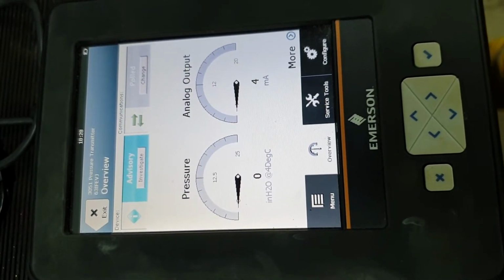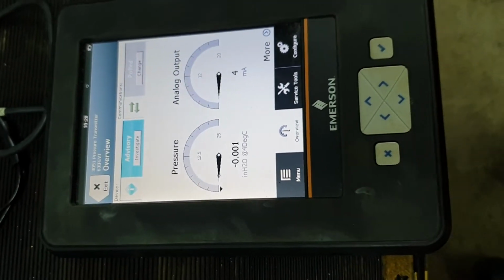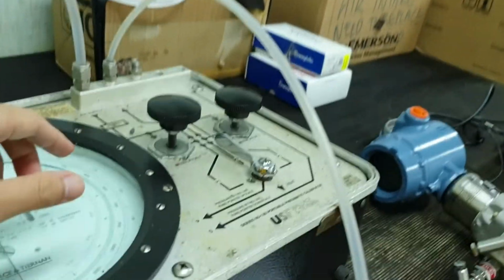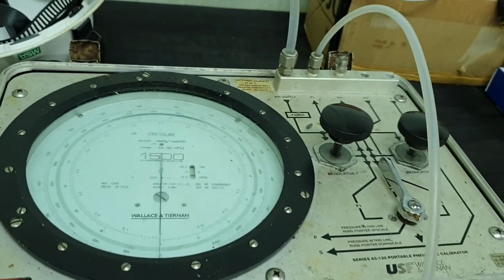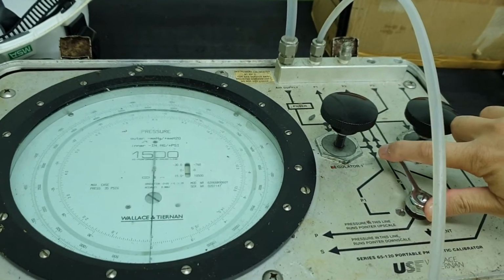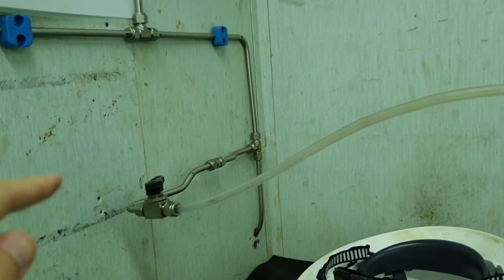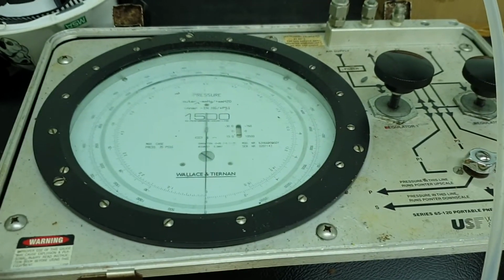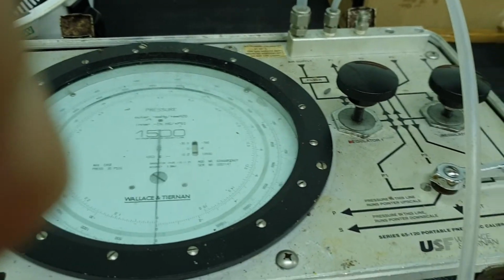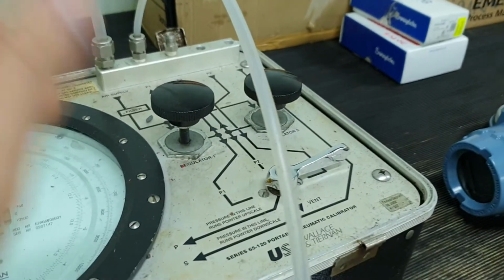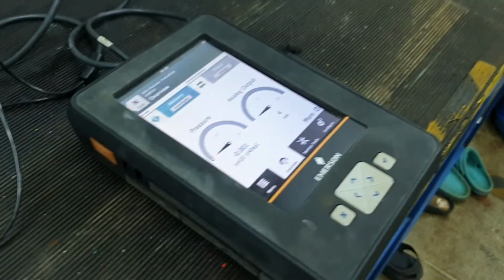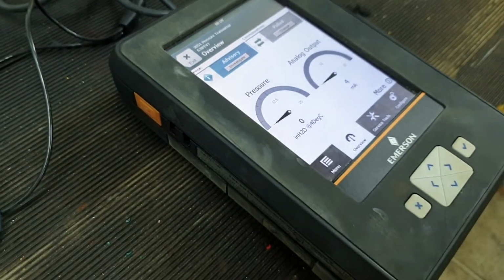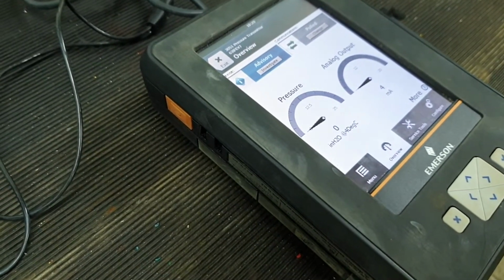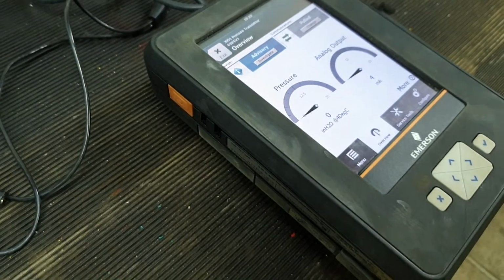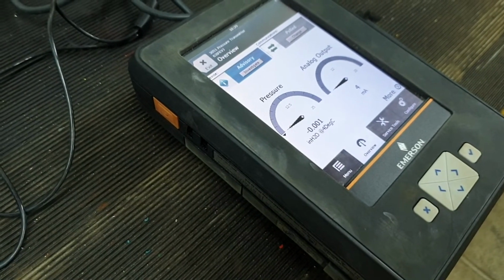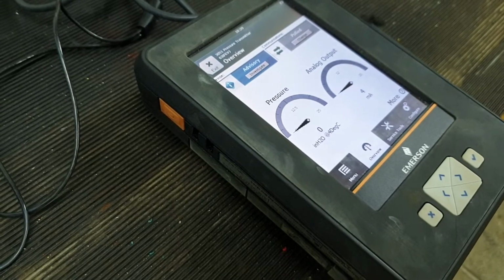Alright, now it's time to play around with the pressure, applying the pressure. What I'm gonna do is apply the pressure into the transmitter by first configuring this to pressure line 1. Of course, I will get the pressure from our main intake. Then the pressure will go into this calibrator unit, and then we will be applying the pressure into the transmitter vent line by slowly increasing this value, and I will be monitoring the figure here. Next, we're going to apply a pressure ramping up from 0% to 100%, or 0 to 25 inches H2O, by stepping it at a scale of 5 times.